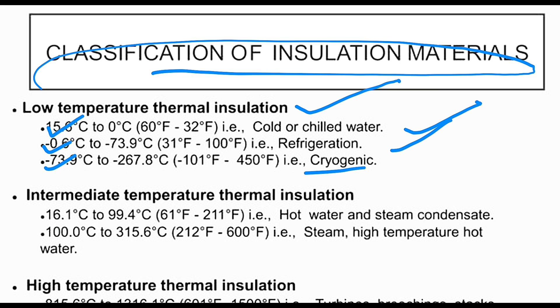Okay. Next is intermediate temperature thermal insulation. 16.1 degrees Celsius to 99.4 degrees Celsius: hot water and steam condensate. Okay. Next is 100 degrees Celsius to 315.6 degrees Celsius: steam, high temperature hot water.